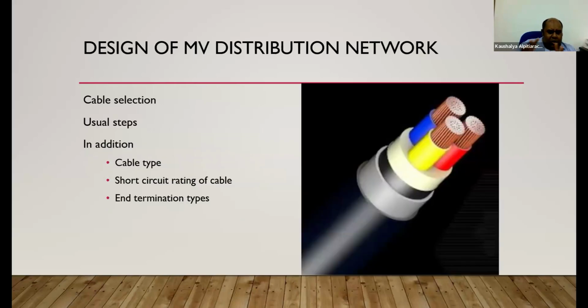Cable selection, usual steps. In addition to that, cable type matters, short circuit rating of cable matters, end termination type matters. Cable type, you may have mostly armored cables with steel wire armored or tape wire armored. If your installation needs burial and subjected to high mechanical forces, steel wire armored cable would be the best choice. The tape wire armor, if it is inside the building and for light mechanical damages, tape wire will be suitable, and it is more flexible than the steel wire armor cable.